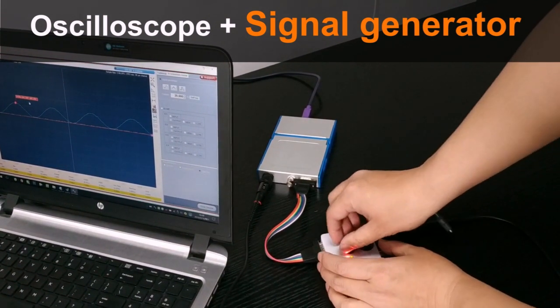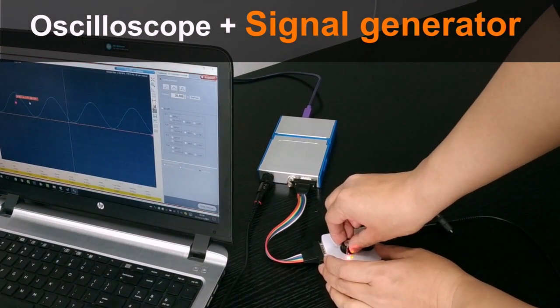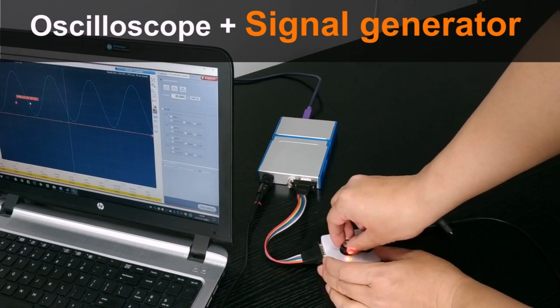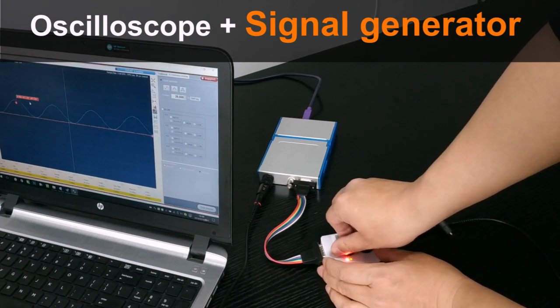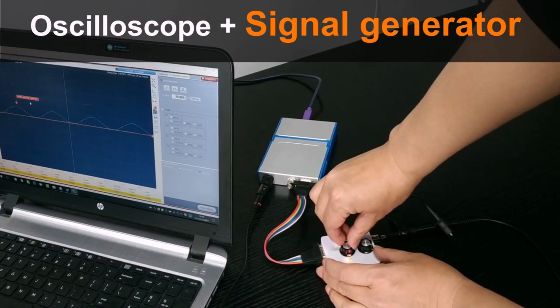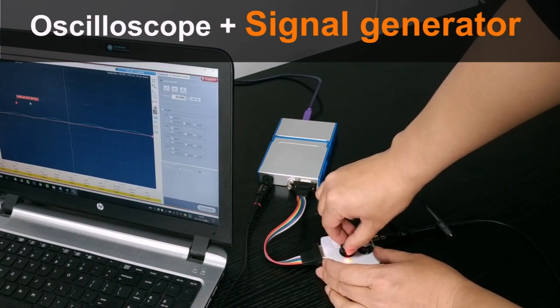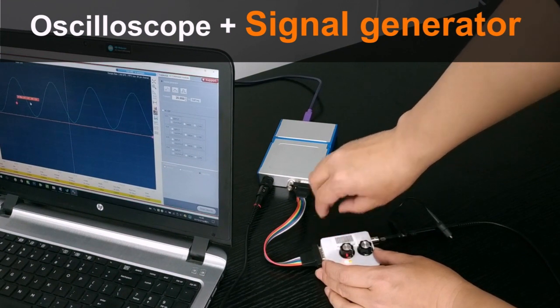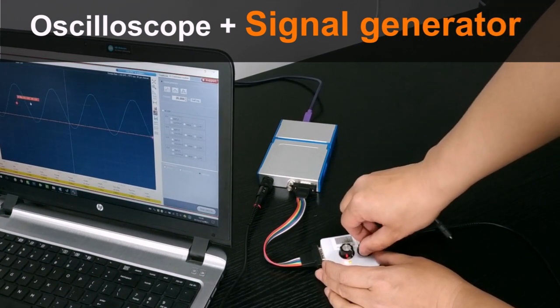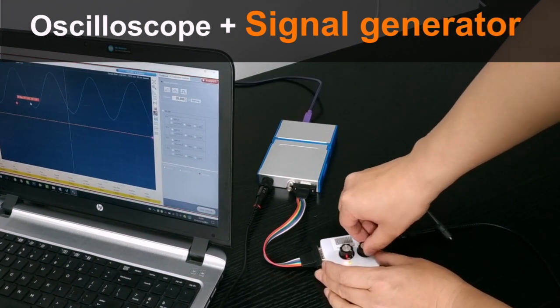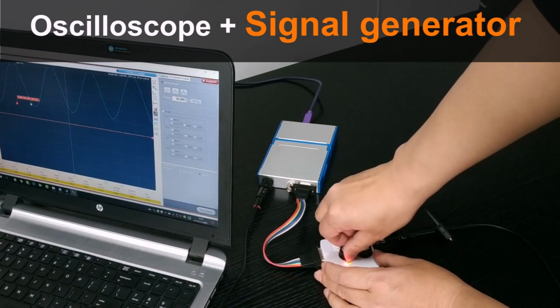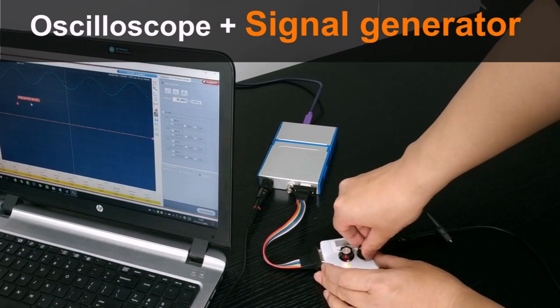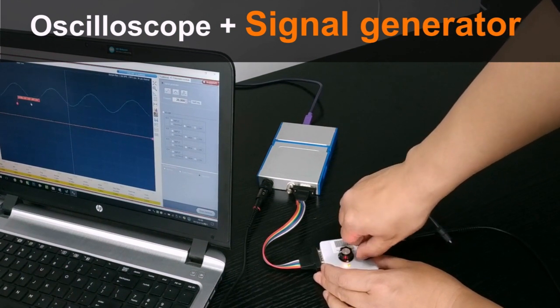On the software we can also activate or deactivate the black panel that shows the digital inputs. Now we can use the software to check the timing of this signal. By using a vertical cursor we can see that all the channels are synchronized including the analog channel.